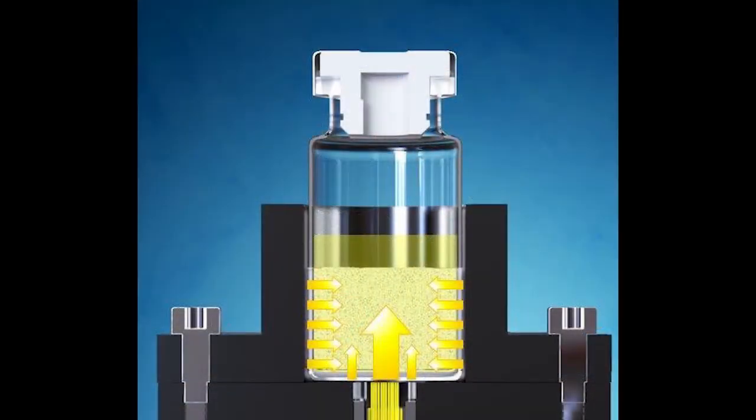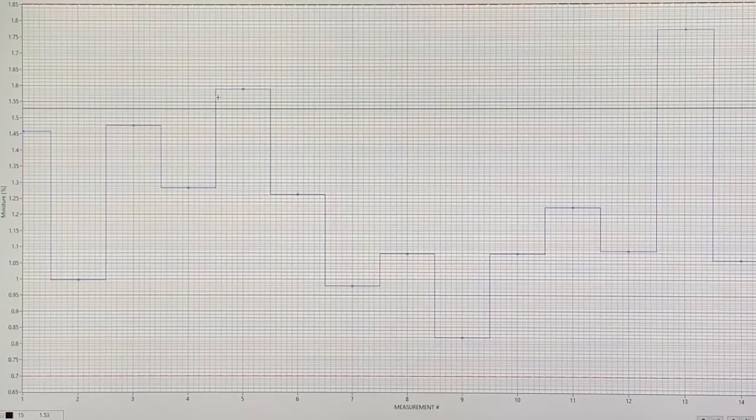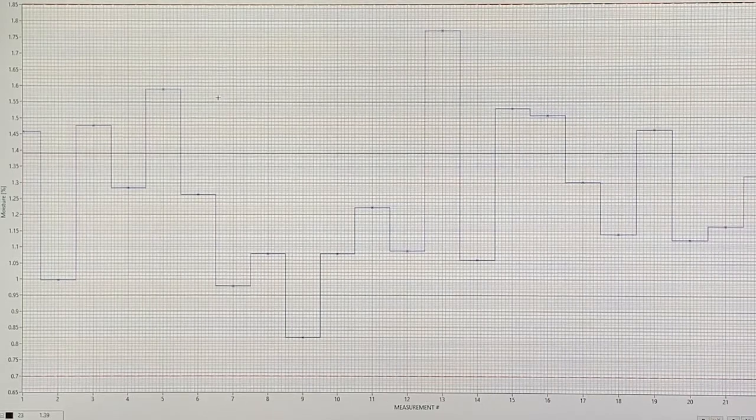LyoEssence measures the residual moisture directly in the product cake, not in the headspace. This means that for every product, a special PLS model needs to be created. This model links the NIR signal to the residual moisture in the cake, and we from GEA are happy to provide this modeling as a service.